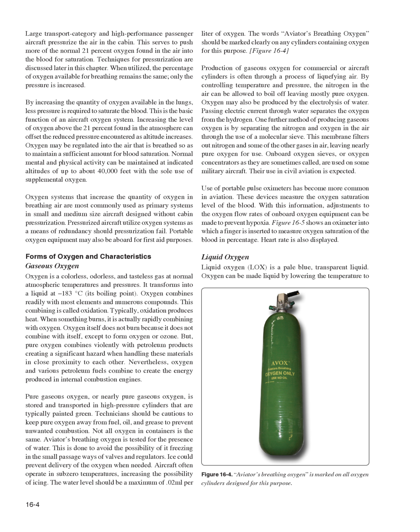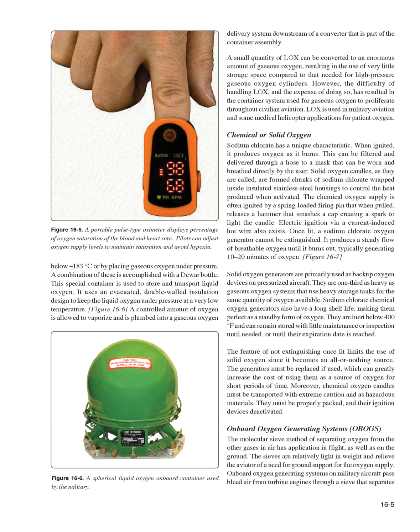Liquid oxygen, LOX, is a pale blue, transparent liquid. Oxygen can be made liquid by lowering the temperature below -183 degrees Celsius or by placing gaseous oxygen under pressure. A combination of these is accomplished with a Dewar bottle. This special container is used to store and transport liquid oxygen. It uses an evacuated, double-walled insulation design to keep the liquid oxygen under pressure at a very low temperature.